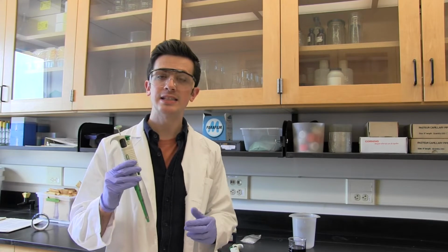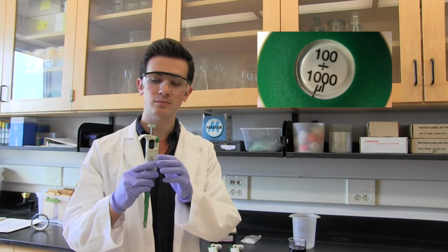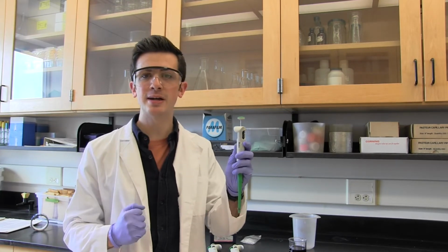This pipette is accurate from 10 to 100 microliters. You may notice that they look exactly the same. So, in order to figure out what your pipette is pre-calibrated for, check the top of the plunger. There should be measurements listed on top of it.